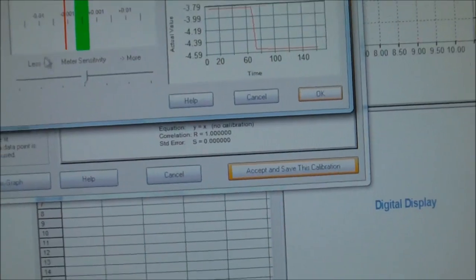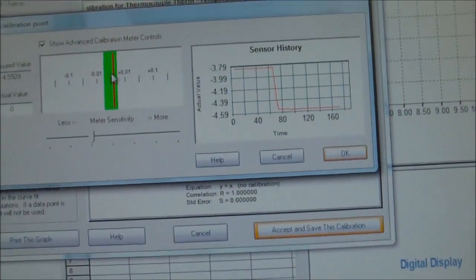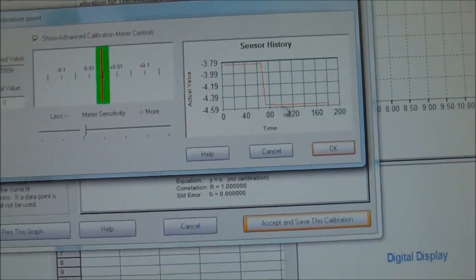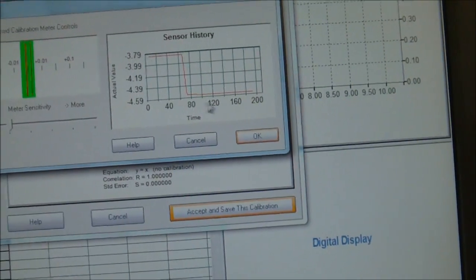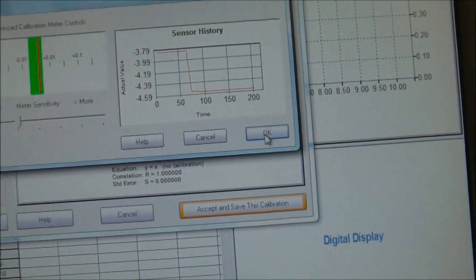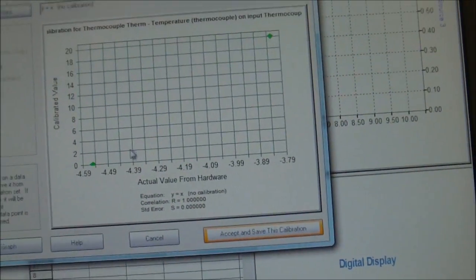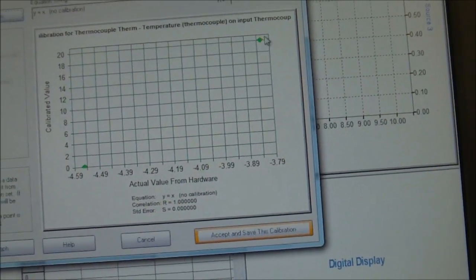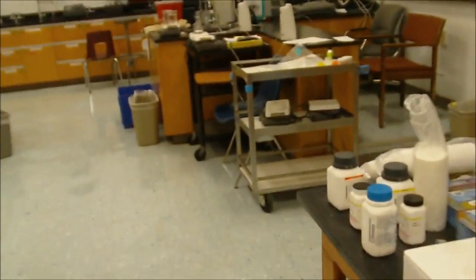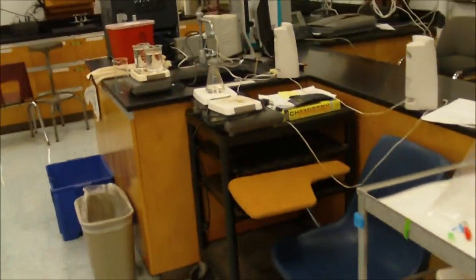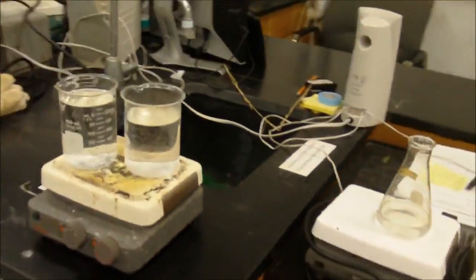If we want to, we could do this to verify that the sensitivity, or that it's stabilizing well enough. We could also look at this curve and see that it's stabilizing also. Then we say OK. Now we have two points, a 0 and a 20 degrees. Now we want to get a warm one. To get a warm one, we have some hot water heating over here. Right, I use the glove.